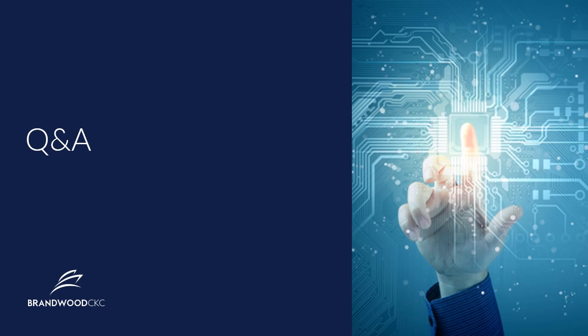There may be some minimum performance requirements that are out there. But one of the unexpected places that you can get a better understanding for performance and analytical performance is the WHO website. If you look at some of their expectations for pre-qualification, they are very specific in their expectations when it comes to analytical performance. And so that can be a very good template for you to use as you're considering the analytical performance for your device. So please have that in mind.